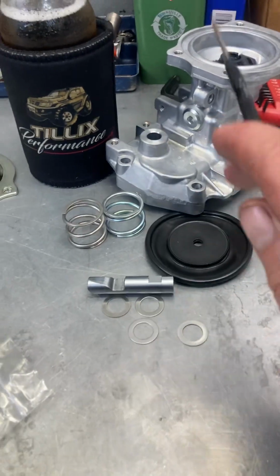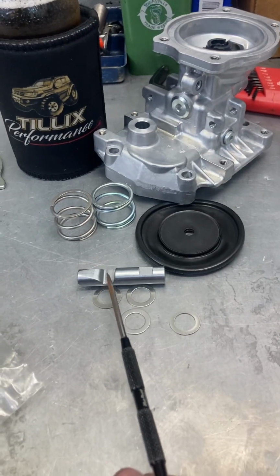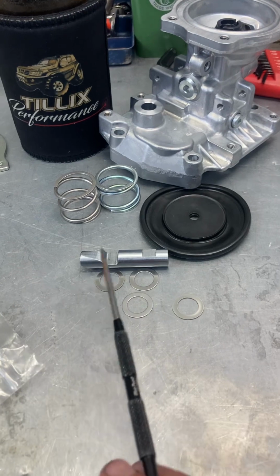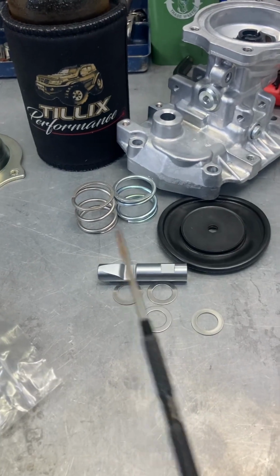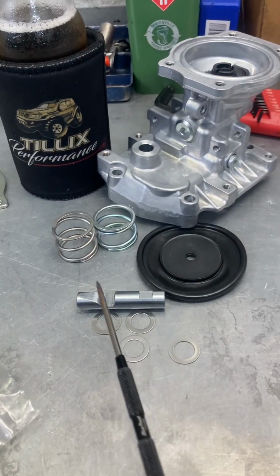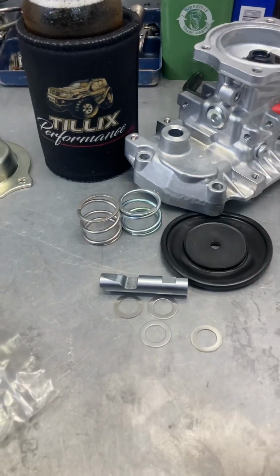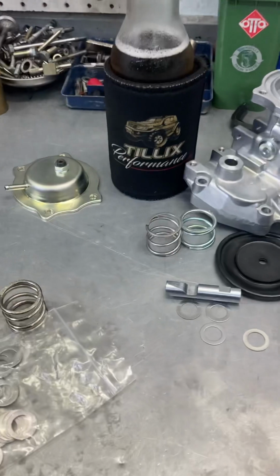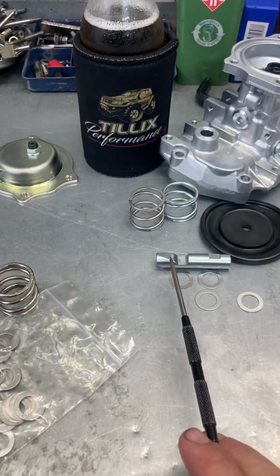Now, that is the best way to do it, because that is increasing the load. We ain't decreasing the load that way, we're increasing the load. So the timing will increase accordingly when you calibrate a load sensing pump correctly.